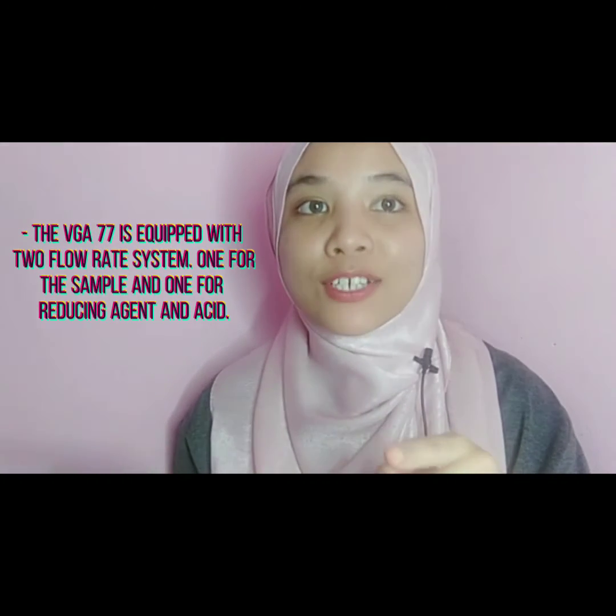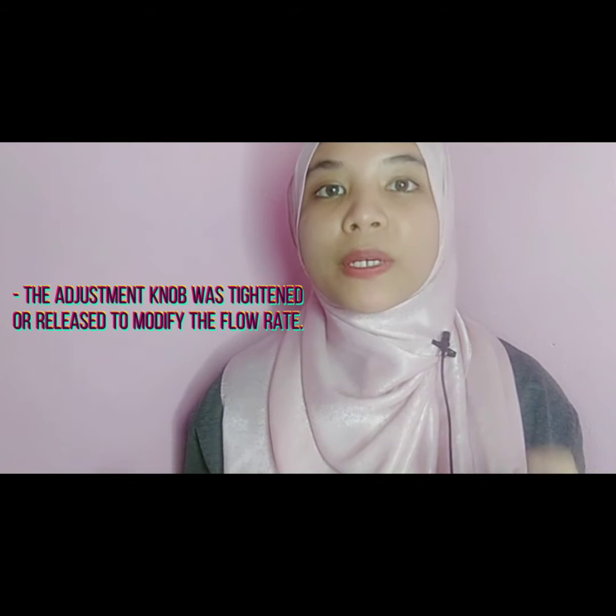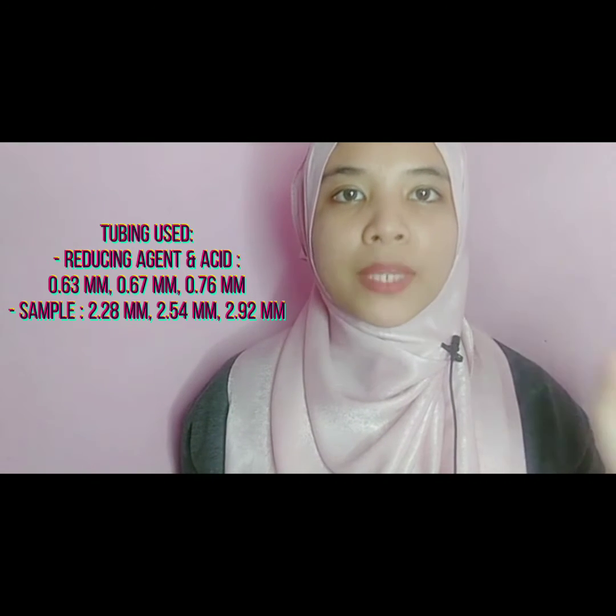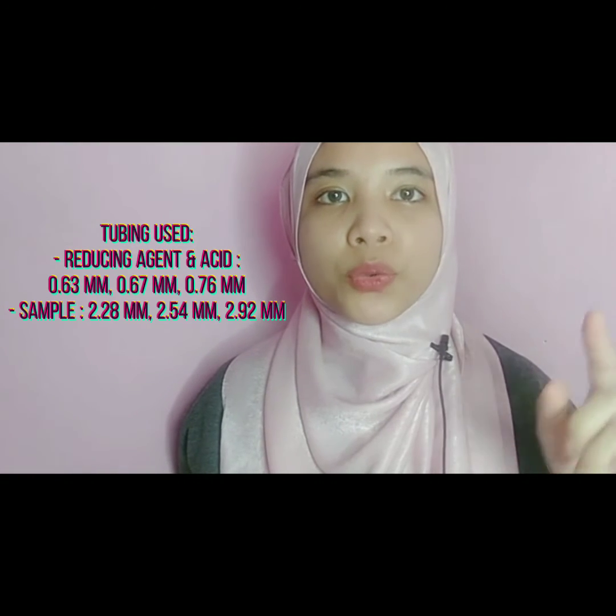The VGA77 is equipped with two flow rate adjustments, one for the sample and one for the reducing agent or the acid. In order to regulate the flow rate, the adjustment knob was tightened or released to modify the flow rate. Just like I mentioned earlier, the internal diameter of the pump tubing also has to be varied to control the flow rate. The tubing used for the reducing agent and acid were 0.63, 0.67, 0.76 mm, while for the sample were 2.28, 2.54 and 2.92 mm.